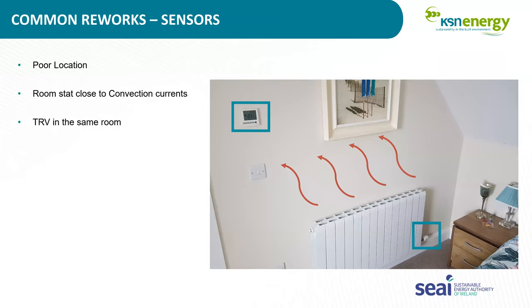This one here, just two issues on this. As you can see by those red arrows, the area over the radiator is going to be warmer than the room itself. Therefore, the position of the stat is not going to give a true representation of what the temperature of the room is. So we'd ask people to consider when installing stats that they're not on top of radiators. Another thing would be in a kitchen where maybe there's a cooker and someone puts on the oven and the kitchen gets nice and warm, but the rest of the house is cold.